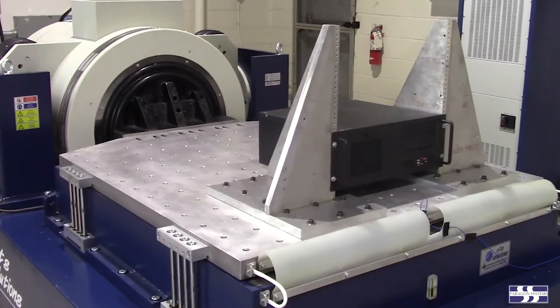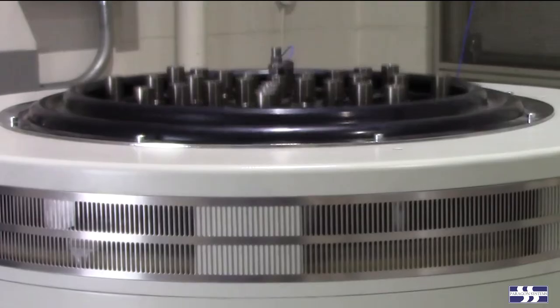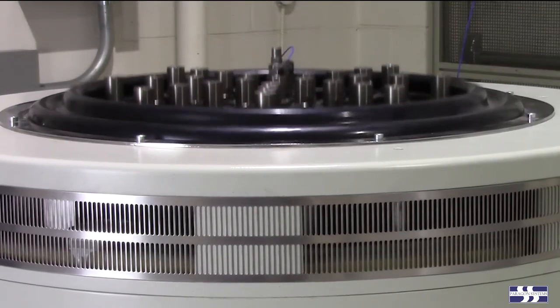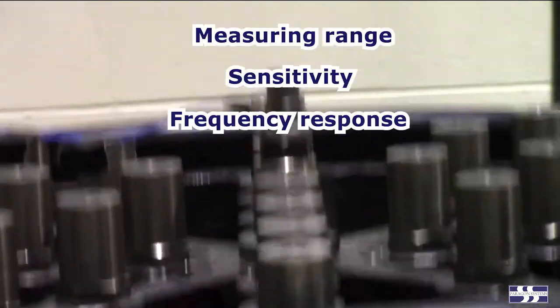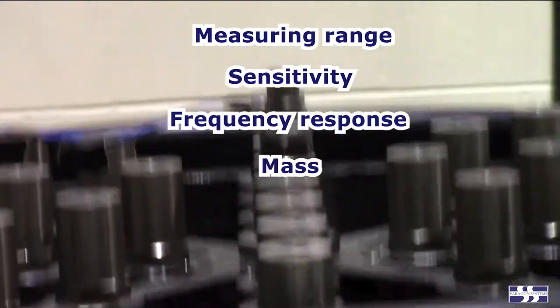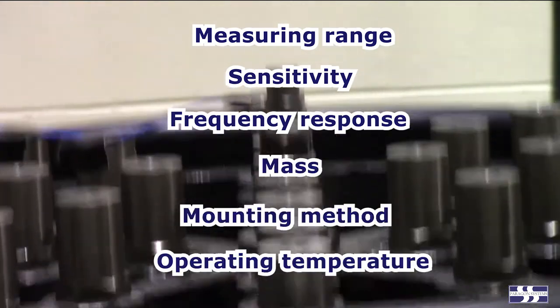Some of the more significant accelerometer characteristics that need to be considered when selecting an accelerometer for a vibration test are measuring range, sensitivity, frequency response, mass, mounting method, and operating temperature.